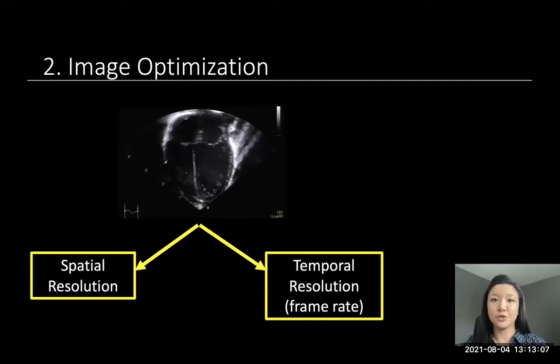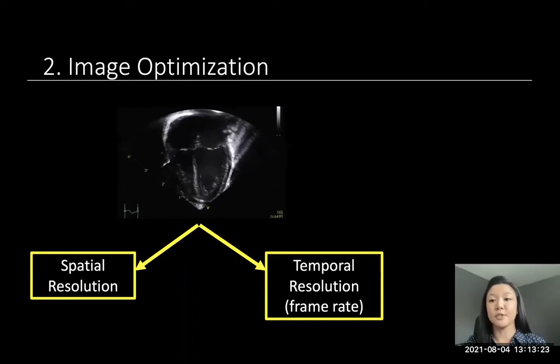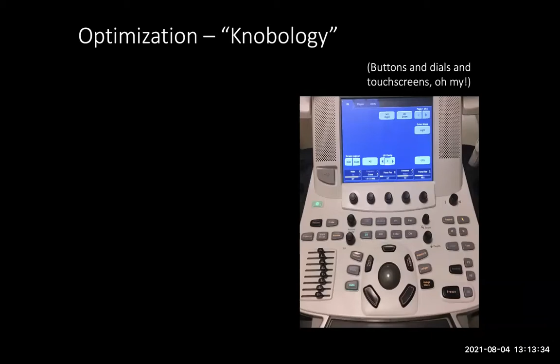Lucky for us, the new neonatal probes have quite good frame rates, but we still should be aware of the image settings that could degrade our temporal resolution. So let's look at what tools we have to do this. Knobology is referring to the function and use of all of the buttons and dials and touchscreen options that we have to optimize our echo images. Echo machines have all of these scanning modes that each have its own set of controls. Then there are other controls that allow us to complete the rest of the echo study, and there are many more than what I've listed.